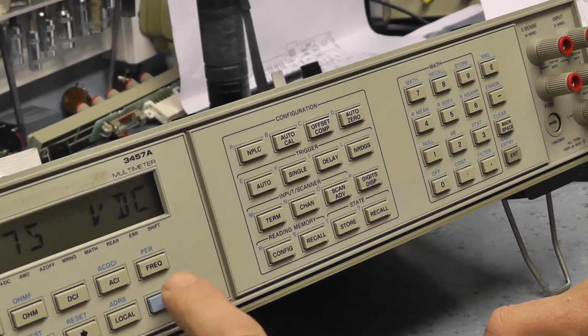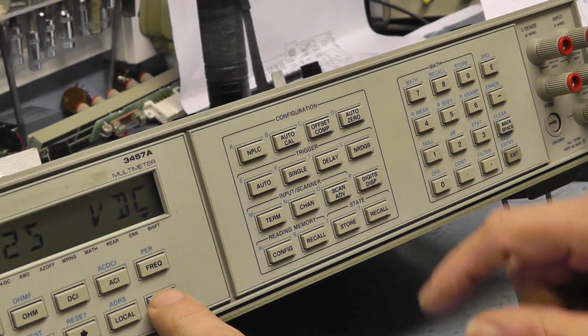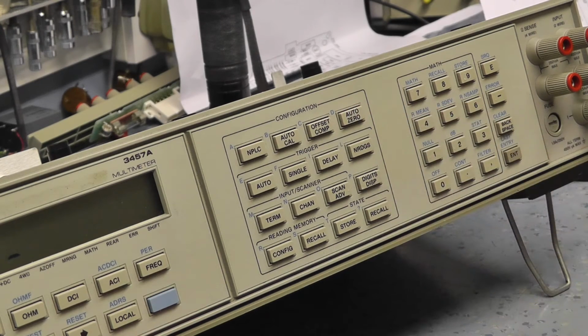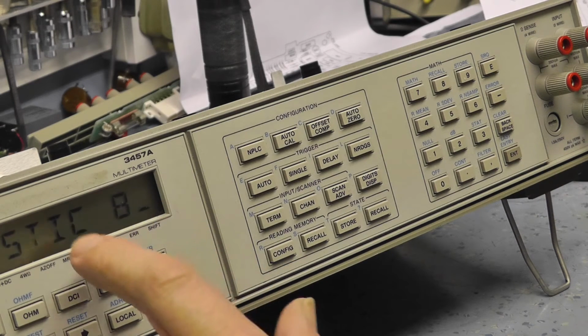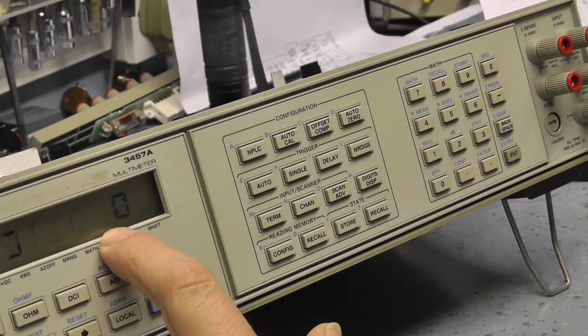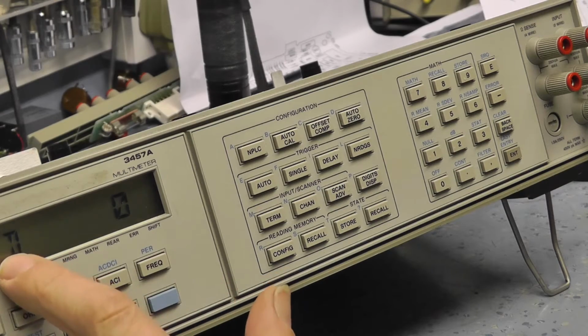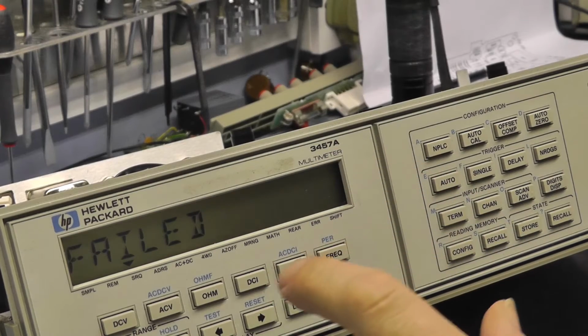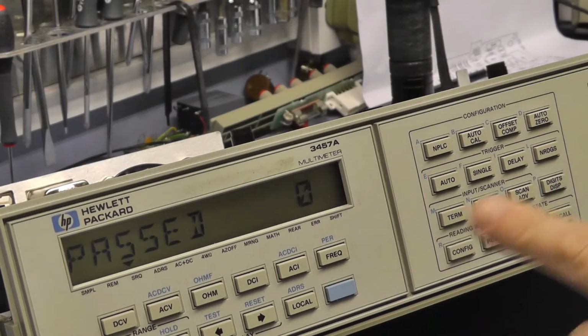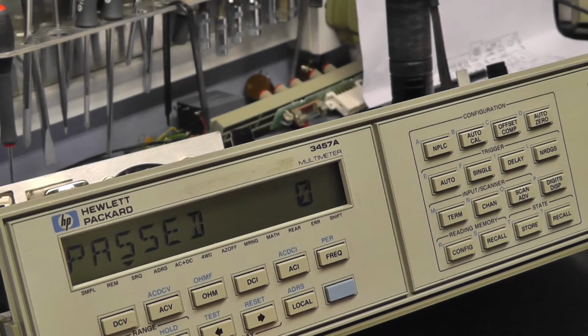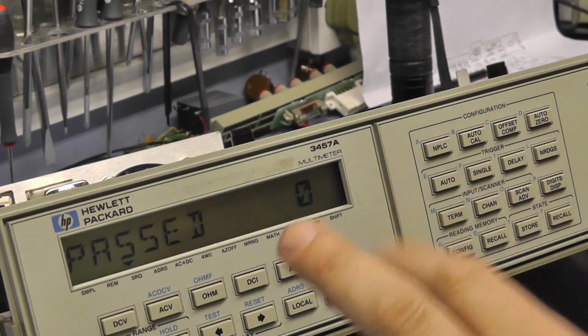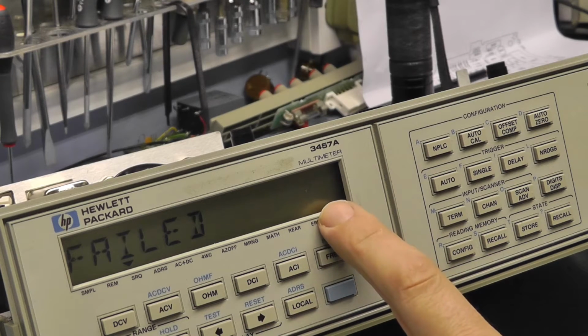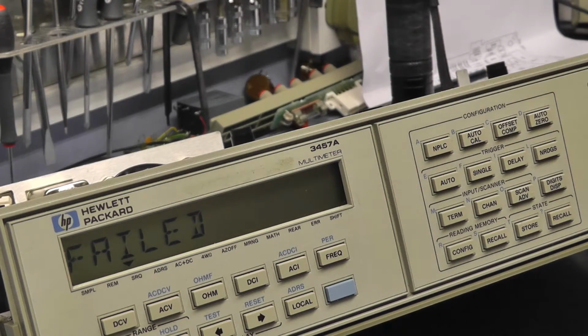So if we go shifted, then auto 0, scroll down to diagnostics, press 8 and press enter, what we should be seeing here is a 0. See, it's passed. Now before that it failed. That's interesting - we go back to pass again, so it's right on the cusp. The unit hasn't warmed up properly, but that's the trimming capacitor where you have to balance out this zero offset, and it's right on the verge now.